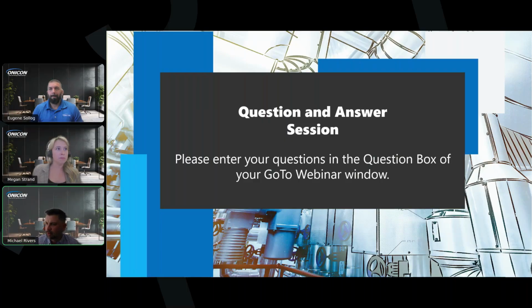Thanks, Megan. A lot of good questions coming in here. This next one's around remote cabling and what's available for remote cable length. Gino, do you want to take that one? Yeah, sure. I think I covered this pretty well in the presentation, but it's a little different, right? We have a low-powered FT3100 version, which is up to 100 feet long, and it starts at 16 feet, with increments of 10 or 20 feet up from 16 feet. The same goes for the FT3200, except that will go all the way to 200 feet with the same increments. If you do need longer, we have a signal amplifier available that will provide for those longer runs if needed.